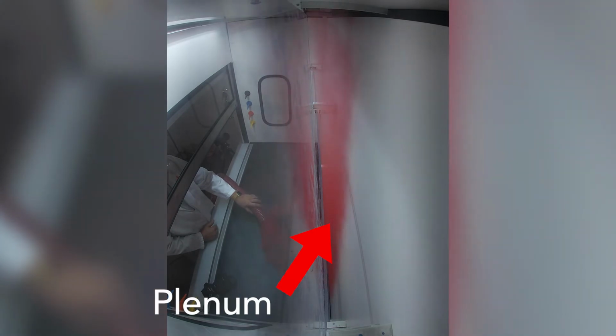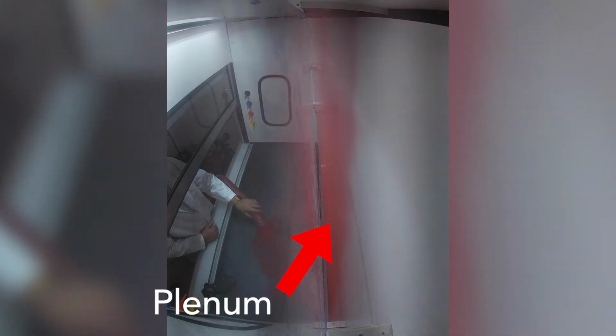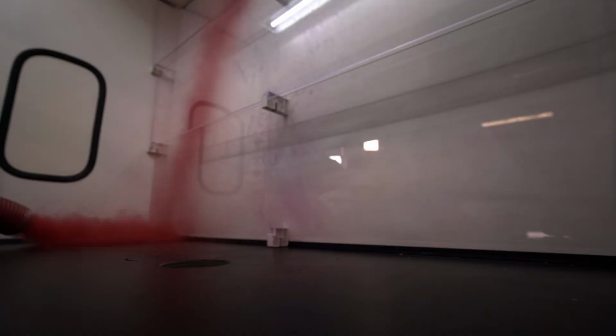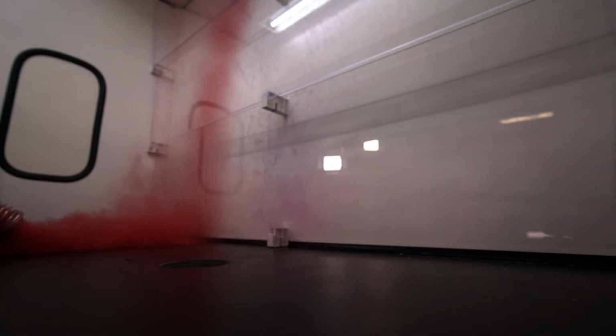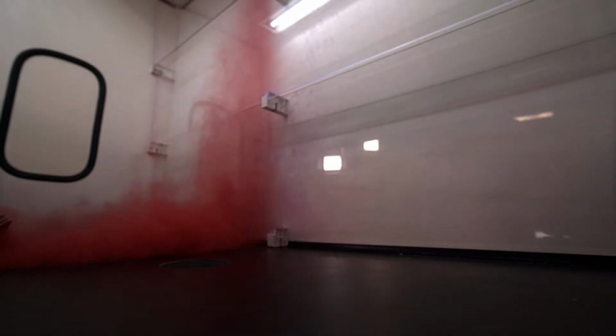Again, the plenum is a space created between the baffles and the back wall of the hood. This special hood was constructed with clear baffles so you can see inside the plenum. By using colored smoke, you can see the path the smoke takes to the exhaust duct. Face velocity is a useful number and provides some indication of overall performance.